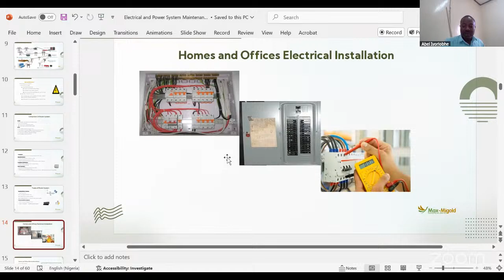Instead, stick to circuit breakers. It trips whether you are there or not. When there is a trip, ensure you check what was responsible for the trip before you reset it. Don't just go and reset it. Ensure that whatever tripped it is unraveled and established. Then, if there is need to correct it, correct that fault and clear it before you reset your system.